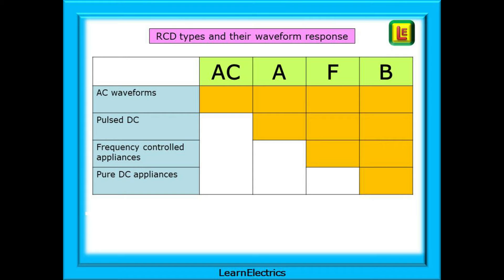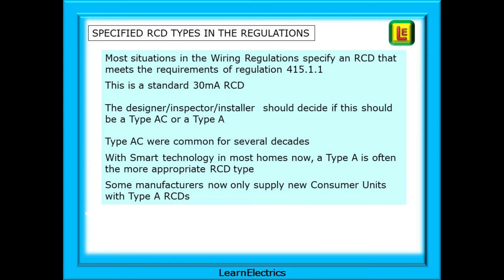With the advent of green energy saving and smart technology, and with so many household appliances and lighting circuits interacting with the user, there are many types of signals being generated within the installation — no longer is it a simple, smooth AC waveform. Most situations in the wiring regulations will specify an RCD that meets the requirements of regulation 415.1.1, which is a standard 30mA RCD. The designer, inspector or installer, however, should decide if this should be a type AC or a type A. Type AC were common for several decades, and with smart technology in most homes now, a type A is often a more appropriate RCD type — some manufacturers now only supply new consumer units with type A RCDs.